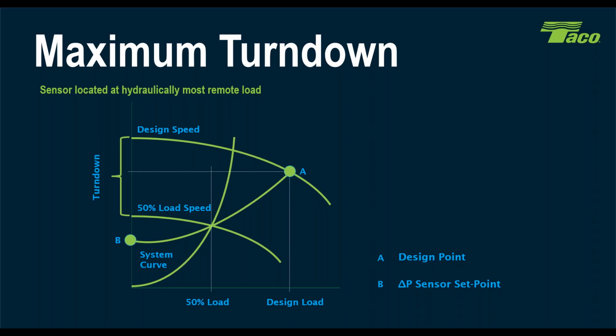As engineers, we know what we designed our system to. We know where that hydraulically most remote load is. That's where that sensor needs to be. So on your drawings, it's a good idea to show the BAS contractor, I want it at air handler 25, because that's my hydraulically most remote load. And in that way, you get the maximum turn down and the best performance out of your pump, because now you're not over pumping the system in any possible scenario.